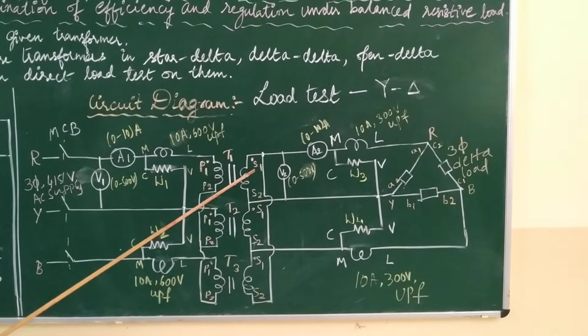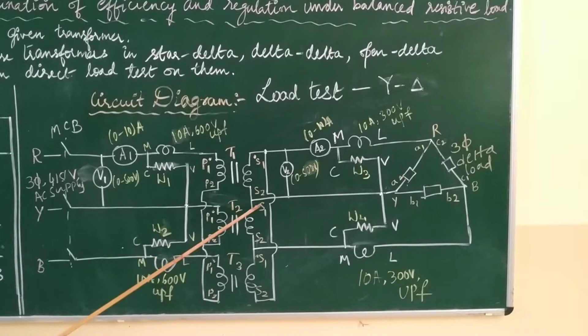the supply. Coming to the secondary side of the transformer, here the secondaries are connected in delta. As you can see, S2 of the first transformer is connected to S1 of the second transformer. S2 of the second transformer is connected to S1 of the third transformer, and S2 of the third transformer is again connected to S1 of the first transformer. So this is nothing but delta connection.